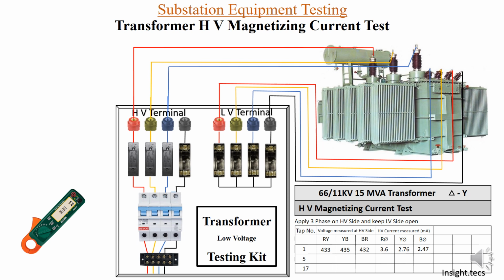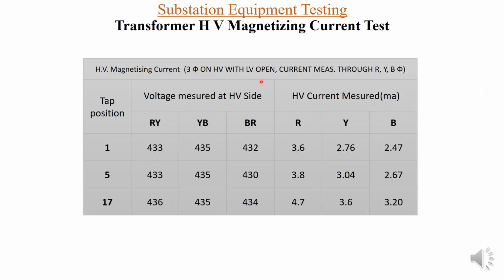Similarly, you can measure for all the taps, for tap number 5 and tap number 17. So these are the results for tap number 5 and for tap number 17. This is the total result of HV magnetizing current. It says 3 phase on HV with LV open. The open circuit or no load test is also another name for HV magnetizing current.